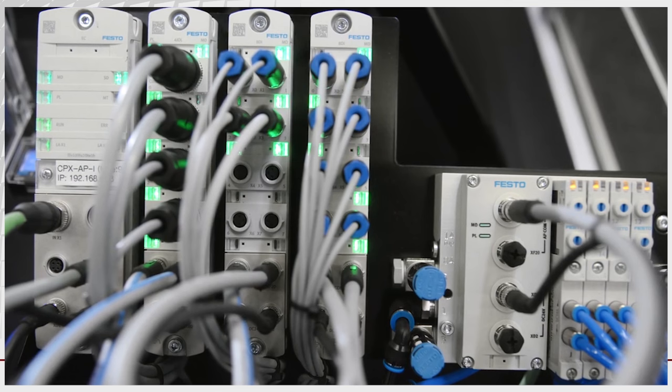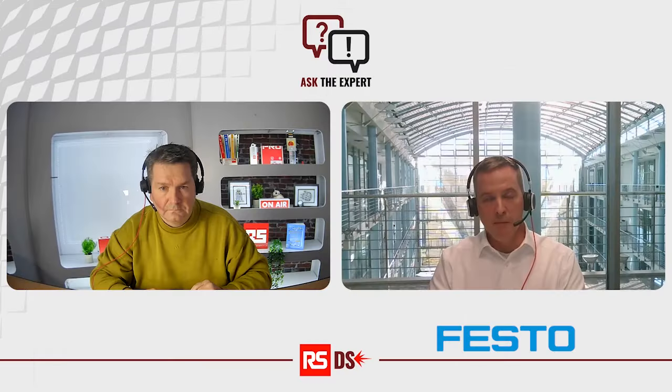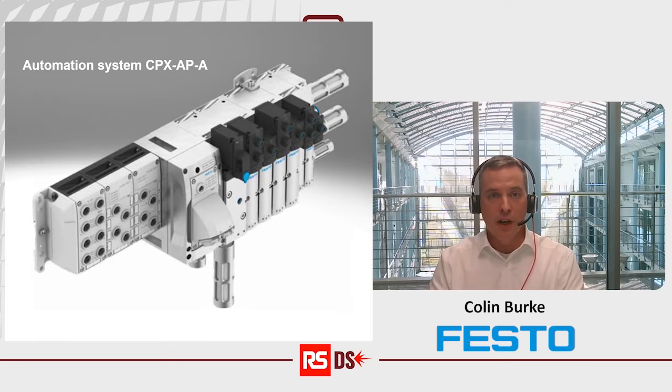But looking from the hardware side, we've got decentralized, that's the CPX AP-I, which you mentioned earlier. So they're remote I/O modules. You see them on the market. They can be put anywhere on the machine, IP65, sometimes IP67. But we also have a modular setup, and that's the AP-A. And it really is only a hardware difference. In the background, the software, the chipset, the communication, the setup tools, it's always the same. What's cool with the CPX AP-A is that you can integrate it onto the valve terminal.